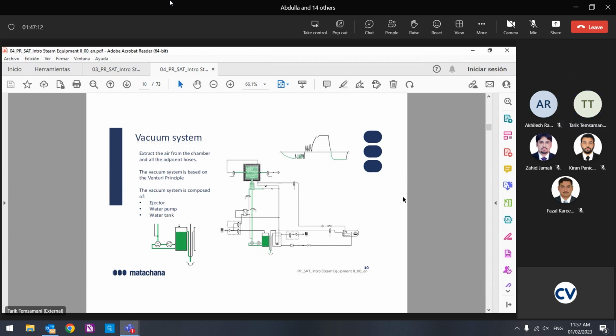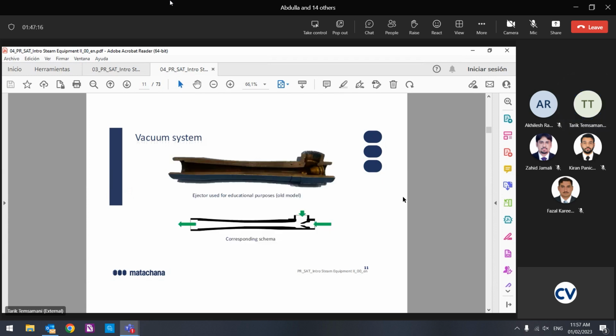Okay, this is for the vacuum circuit, the vacuum system. This is the ejector. For the ejector, we put water from the pump at this place, and we return it to the tank at the other place. With these movements, we create a venturi on this upper side, and we remove the air from the chamber from this side.